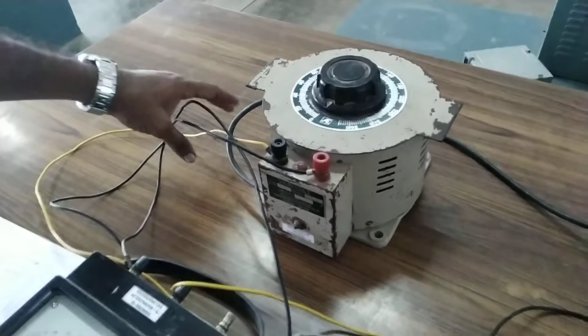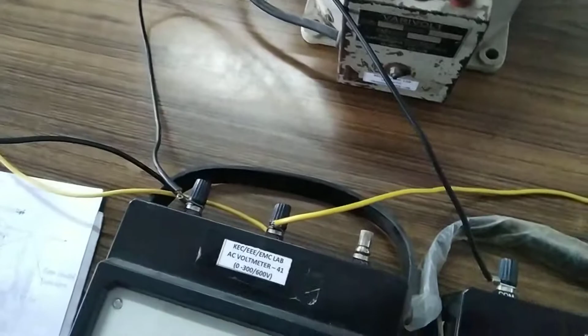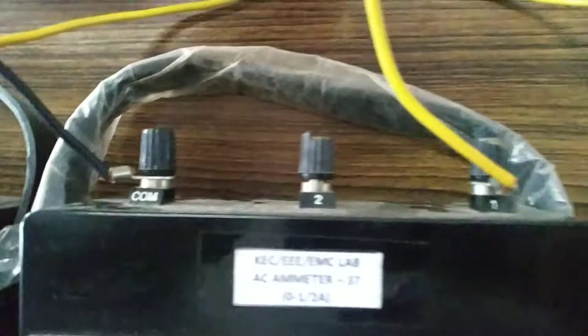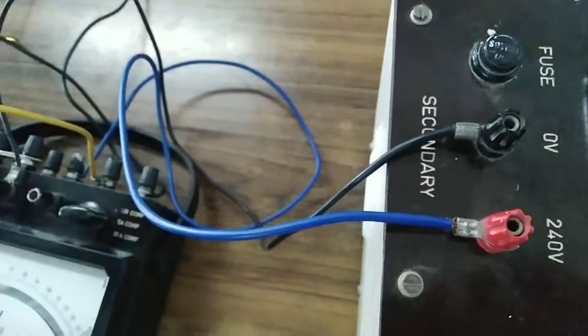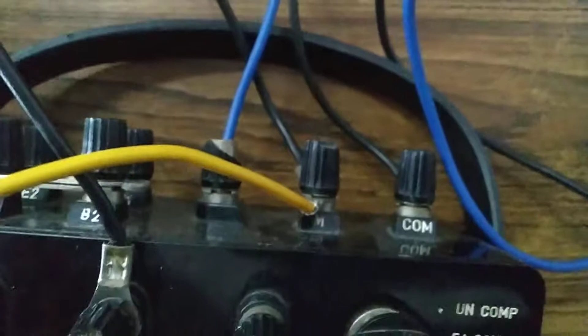Now we see the circuit connections. The single phase supply is connected to the auto transformer. From the auto transformer phase, connection is given to the voltmeter. From the voltmeter common, with the help of a wire, you connect to the common of the ammeter. From the 1 amp terminal of the ammeter, connection is taken and given to M in the wattmeter. M and C are short circuited with the help of a wire.